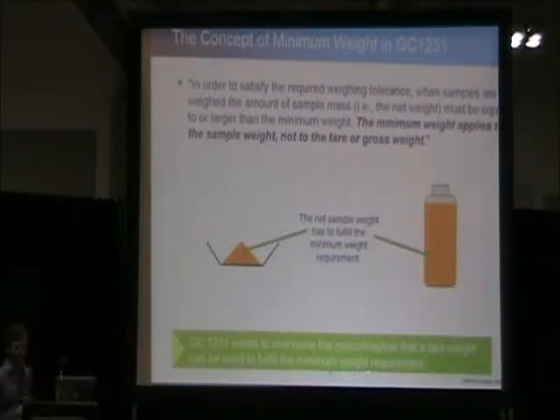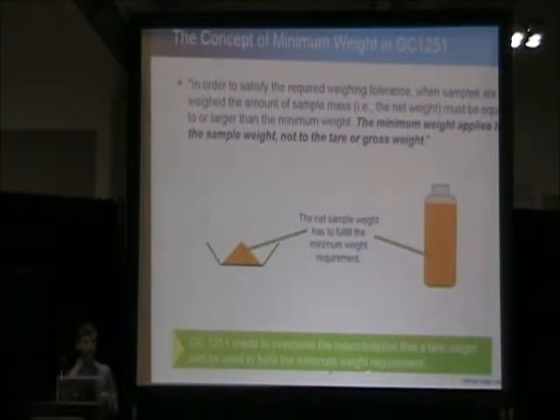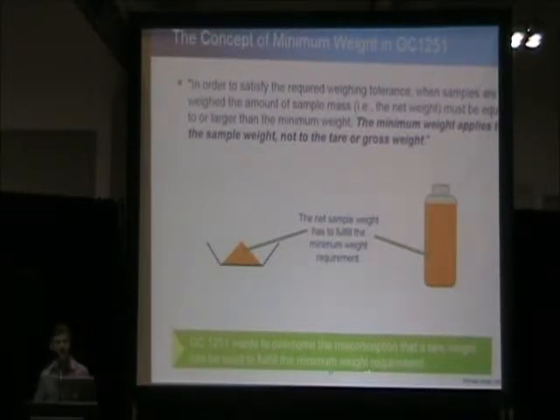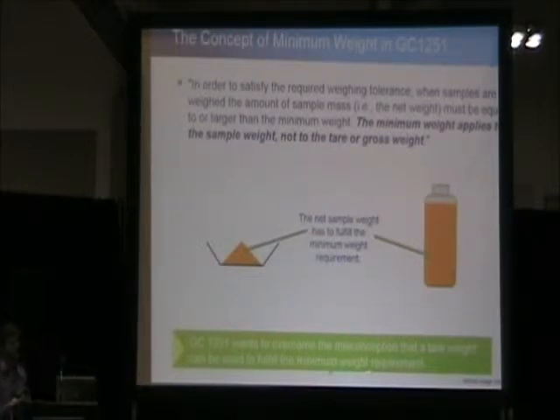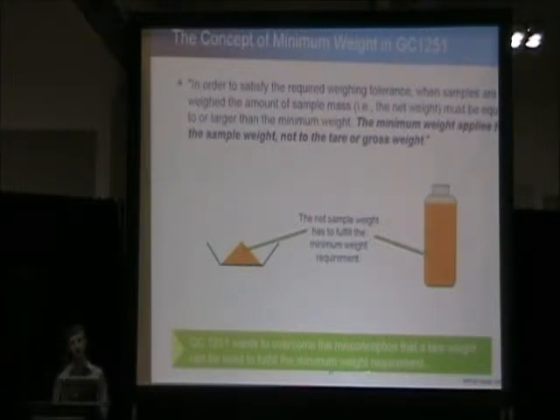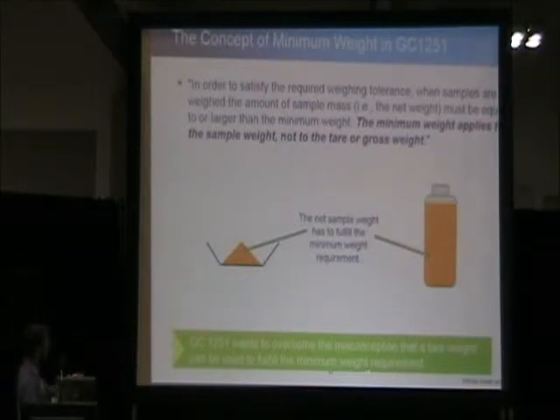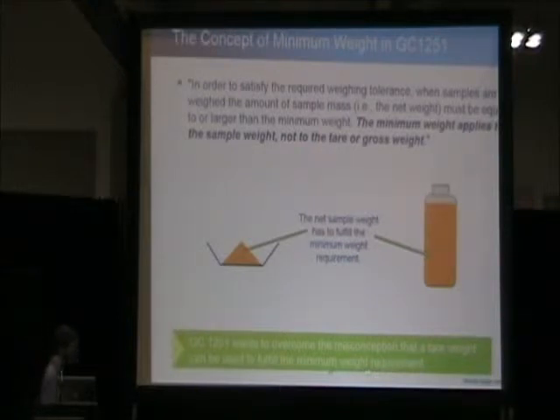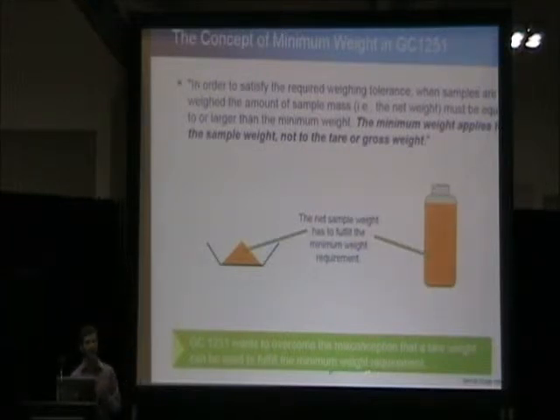You're weighing an API for a particular drug. That needs to be 1 milligram. Some people will assume if you take a weigh boat or a piece of weigh paper and place it on that instrument and go past that 1 milligram, that you've actually been able to supersede your minimum weight. This is not the case, and it is explicitly stated in Chapter 1251 of USP that the minimum weight applies to the sample weight and not to the tare or gross weight. What this means is that when we talk about minimum weight for the rest of this presentation, we're talking about the sample weight that you're trying to actually measure.